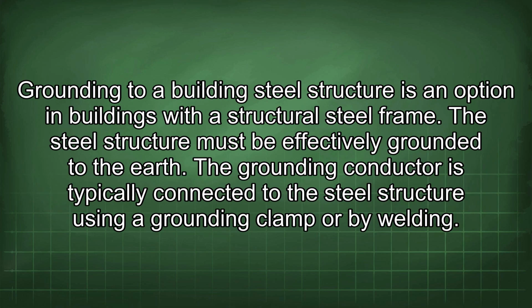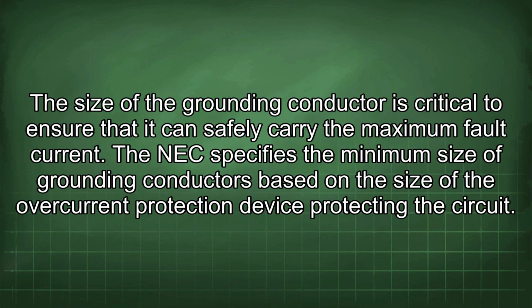Grounding to a building steel structure is an option in buildings with a structural steel frame. The steel structure must be effectively grounded to the earth. The grounding conductor is typically connected to the steel structure using a grounding clamp or by welding. The size of the grounding conductor is critical to ensure that it can safely carry the maximum fault current.